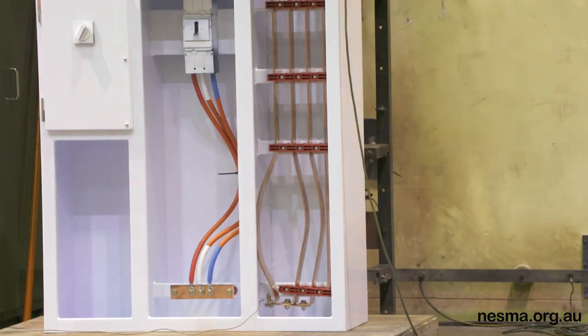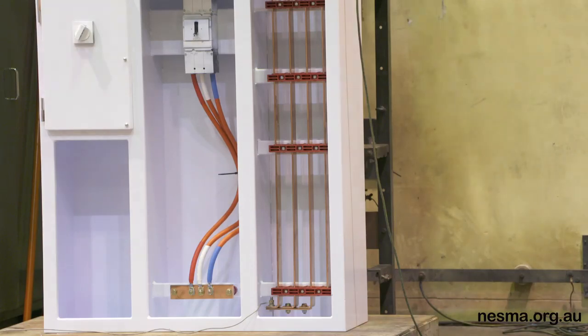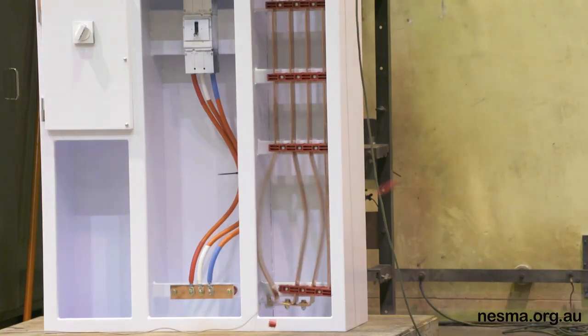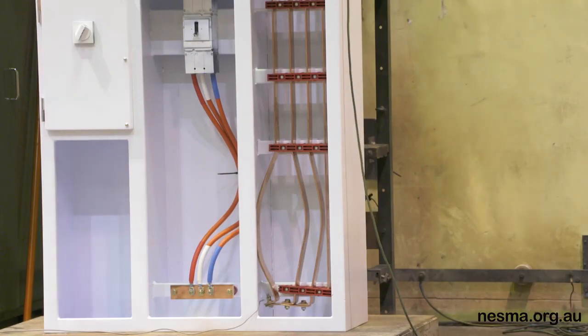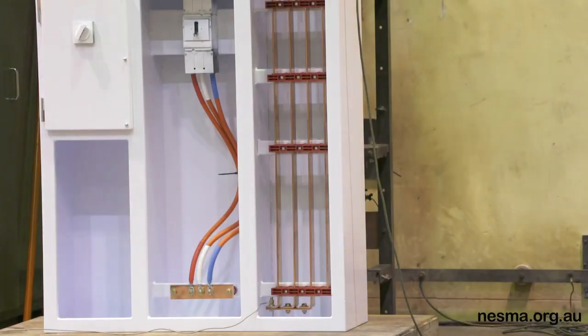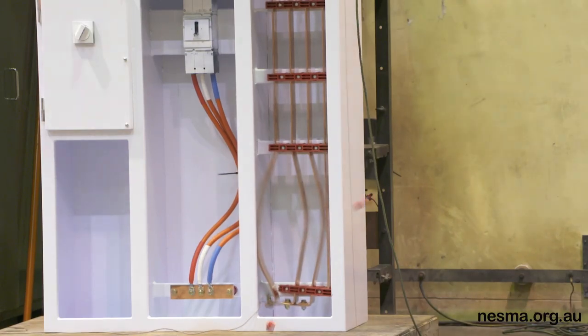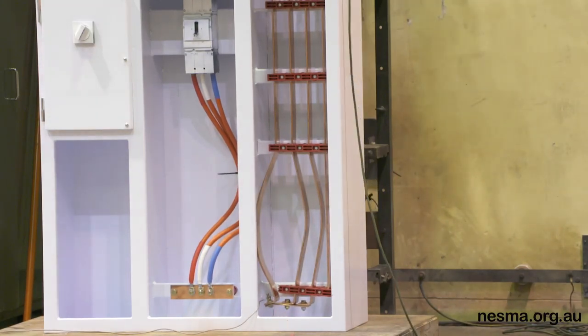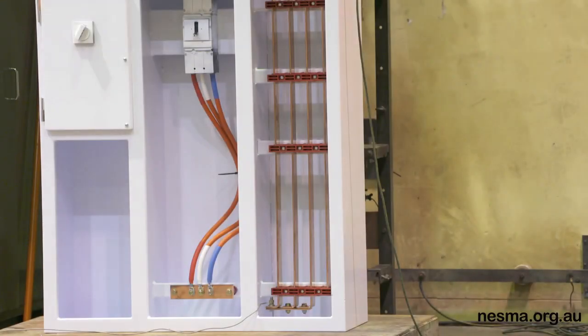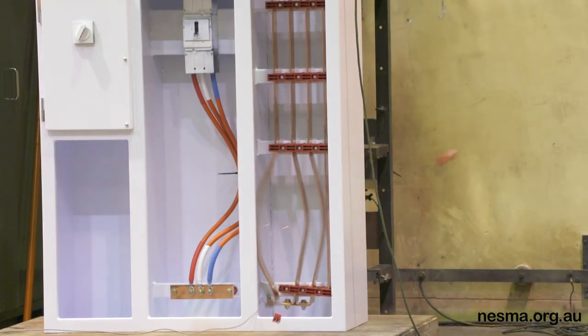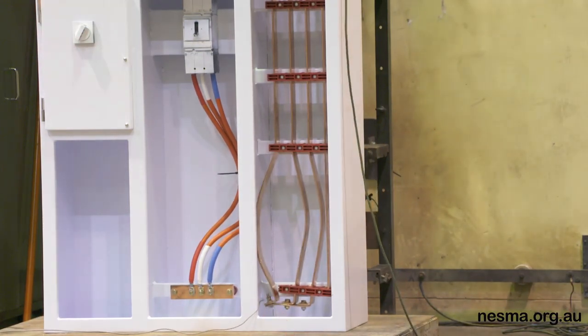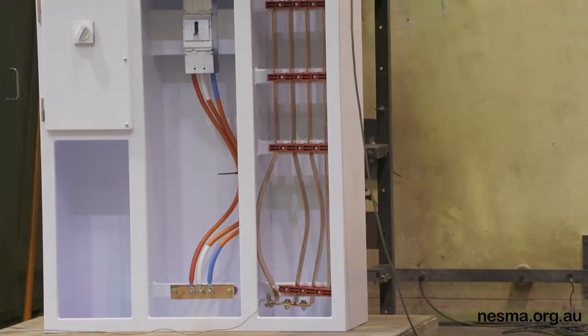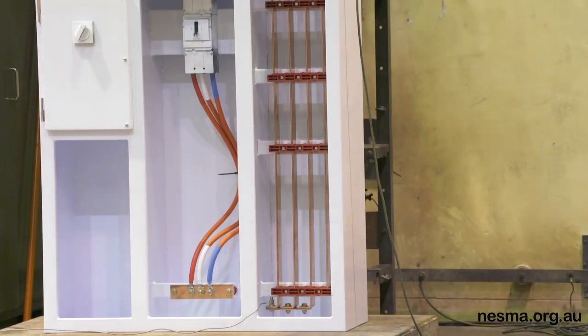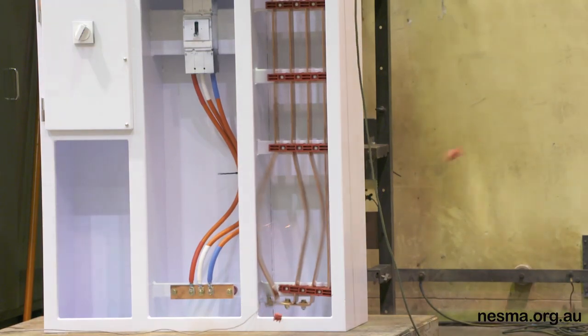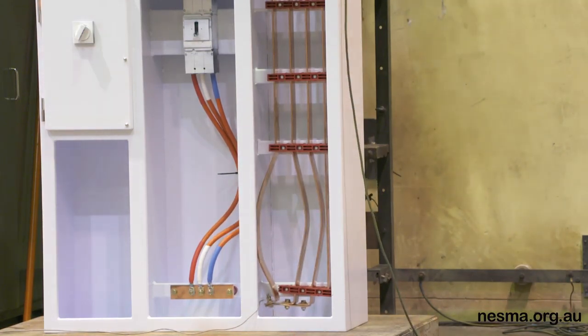And you may also pick up a little bit of slight arcing where that left-hand bar is hammering onto the side of the enclosure. Now, there isn't much arcing there because, even though we're applying 400 volts onto the busbar system for the test, the voltage rise from the short circuit position to that 200 mil up the bar system is not great enough to create a lot of arcing. If it was open circuit, then we would have had the full voltage to earth in that area.